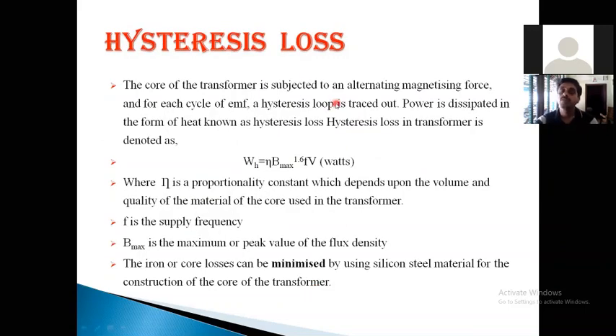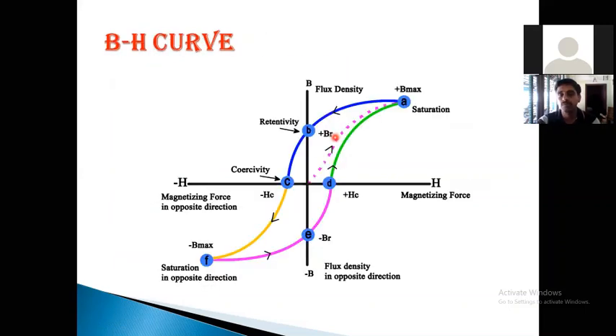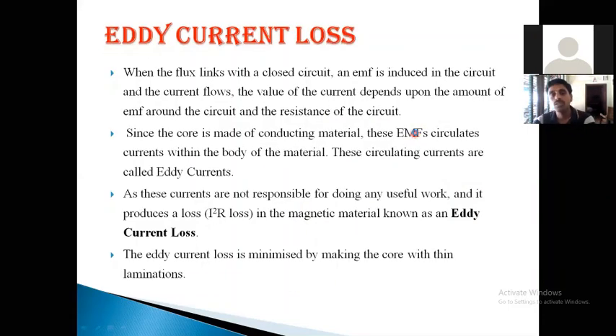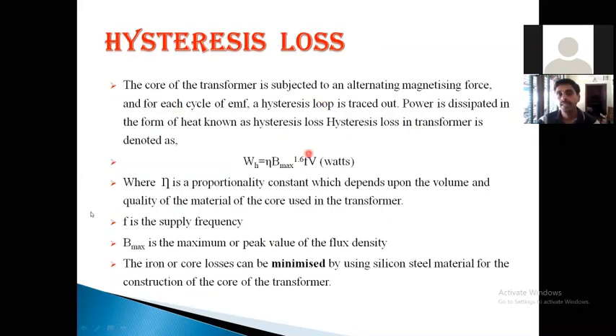So there will be two types of losses in the transformer. This you should know: hysteresis loss and eddy current loss. You know about the hysteresis loss, already seen in the BH curve. This means magnetization, demagnetization, retentivity, saturation, and coercive force. These are all things we have discussed in the first unit itself. Because this current is varying sinusoidally, with magnetization and demagnetization, there will be hysteresis loss in the core. Those hysteresis losses can be represented, as I said, as Steinmetz constant into B max to the power 1.6 into F into V.